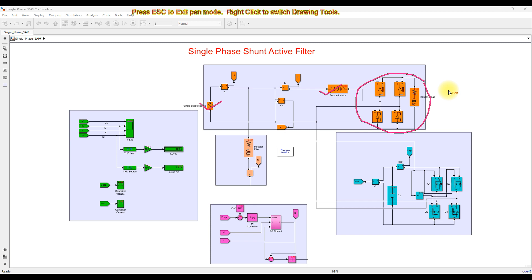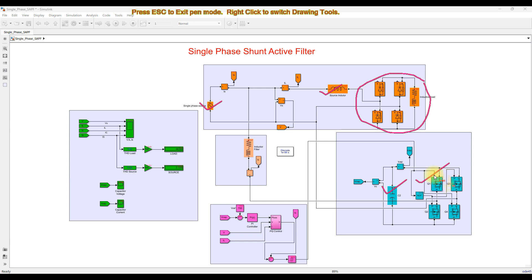In order to avoid that problem, we use a shunt active filter. Here we are using a single phase shunt active filter having an H-bridge inverter and a capacitor. This capacitor will be used for supplying the reactive power based upon the nonlinear load, and the single phase H-bridge inverter will be controlled by means of a control concept.